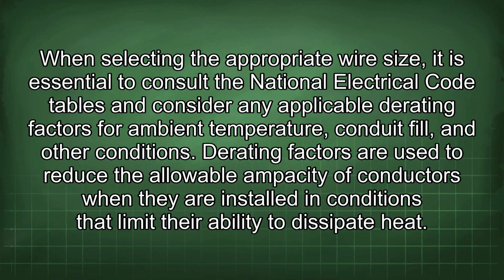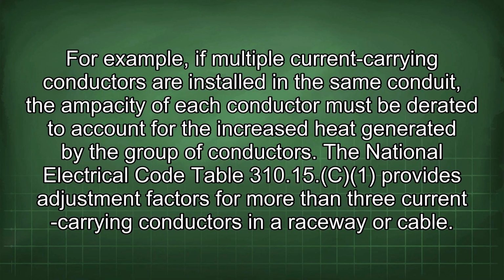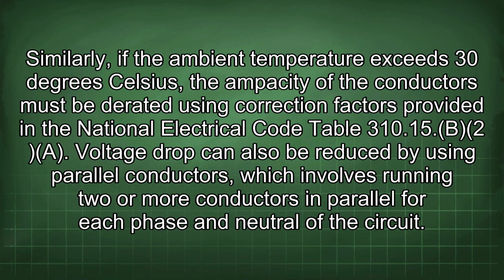Derating factors are used to reduce the allowable ampacity of conductors when they are installed in conditions that limit their ability to dissipate heat. For example, if multiple current-carrying conductors are installed in the same conduit, the ampacity of each conductor must be derated to account for the increased heat generated by the group of conductors. The National Electrical Code Table 310.15 provides adjustment factors for more than 3 current-carrying conductors in a raceway or cable. Similarly, if the ambient temperature exceeds 30 degrees Celsius, the ampacity of the conductors must be derated using correction factors provided in the National Electrical Code Table 310.15(B)(2)(a).